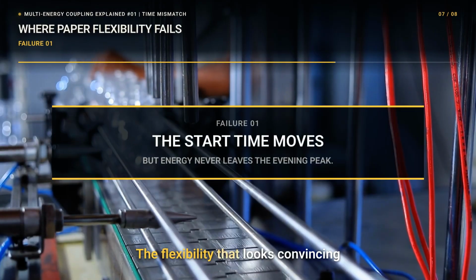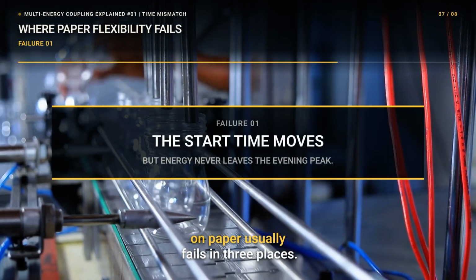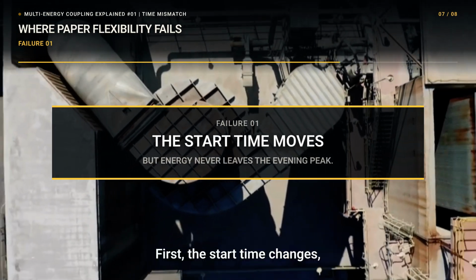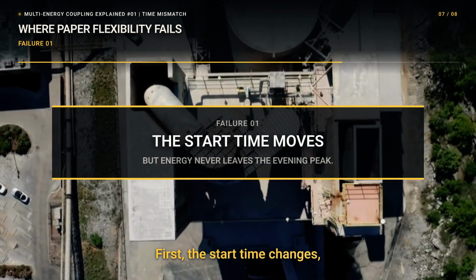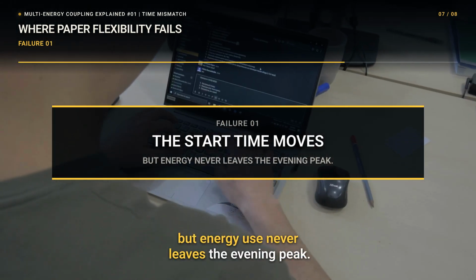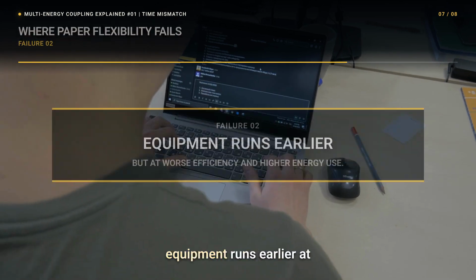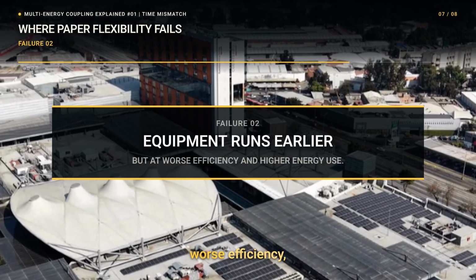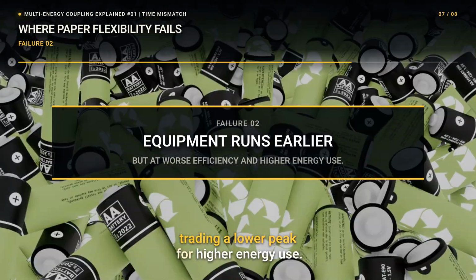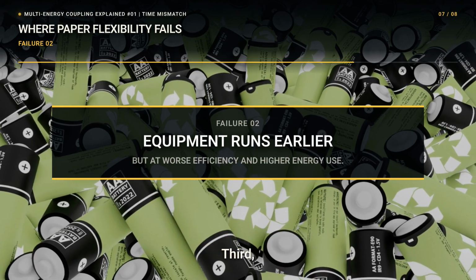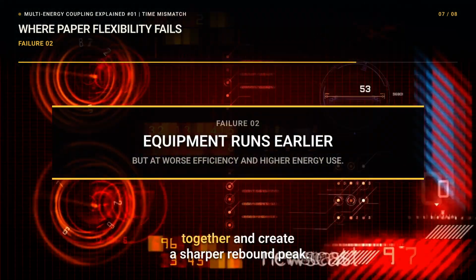The flexibility that looks convincing on paper usually fails in 3 places. First, the start time changes, but energy use never leaves the evening peak. Second, equipment runs earlier at worse efficiency, trading a lower peak for higher energy use. Third, deferred loads return together and create a sharper rebound peak.